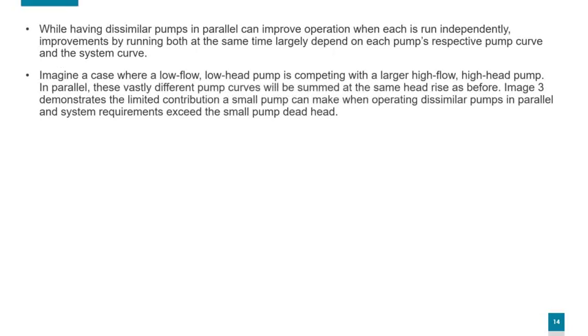So as we've seen in the curves, while having dissimilar pumps in parallel can improve operation when each is run independently, improvements by running both at the same time largely depend on each pump's respective pump curve and the system curve. Imagine a case where a low flow, low head pump is competing with a large flow, high head pump. In parallel, these vastly different pump curves will be summed at the same head rise as before, as we see in the image demonstration.